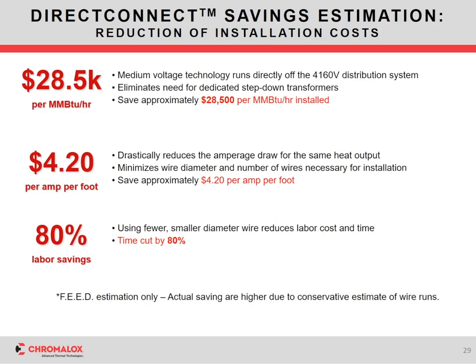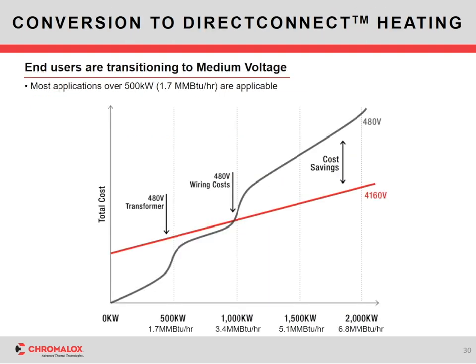Now again, every installation is a little bit different, every on-site, but this slide is just to give some overall numbers. If you have a medium voltage system that runs directly off a 4160 volt distribution system, like the offshore platform, that's where you could save roughly $30,000 per million BTUs per hour. Also, the wiring is another way to look at it. That's where you can save a little over $4 per amp per foot of wire. And then with labor savings, that's 80% and above for a medium voltage system, because those labor rates don't have to be included, with a lower amount of wires. Now again, these are estimates based on a feed study. Depending on your wiring runs and your on-site locations, they can be slightly lower or higher, but this is to give you some ballparks for if a medium voltage system makes sense for you.